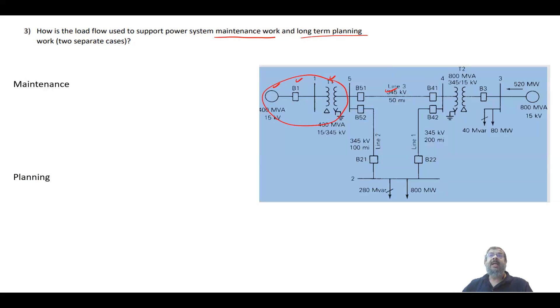The load flow will help us see what would be the status of the power system if we take any unit for maintenance and knowing the load profile as well. We might select the time that the demand is less. That's also very important for when to schedule the maintenance. Many people like to schedule maintenance in the winter not in the summer because the demand is less, maybe in the early morning or late at night because the demand is less.